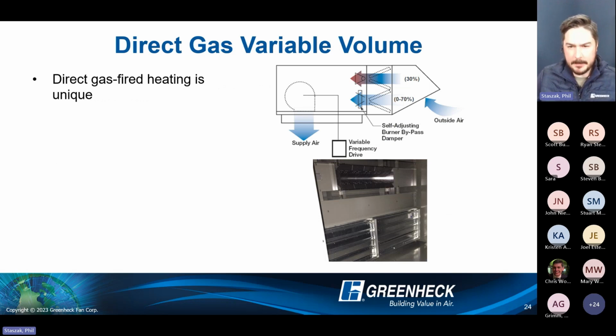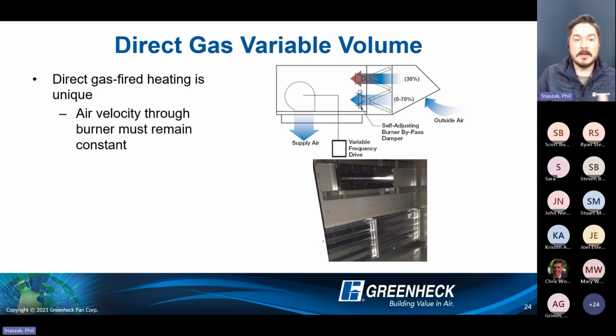So the barometric damper located right here underneath this burner section allows for the at-design airflow. That damper basically cracks open and allows that pressure drop to stay the same at design. And then as you start to lower or drop the required amount of outside air, that damper starts to kind of creep closed, forcing the excess air up top, always maintaining a certain pressure drop across that burner for good, safe, clean combustion, no matter what, at design airflow or minimum airflow. So air velocity needs to remain constant across that burner for that good quality combustion.